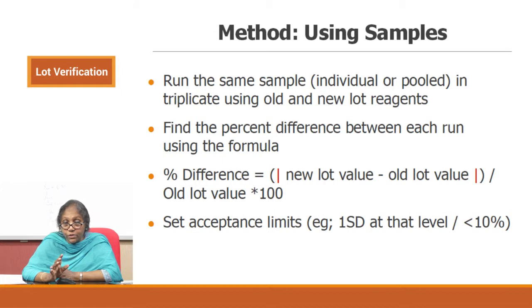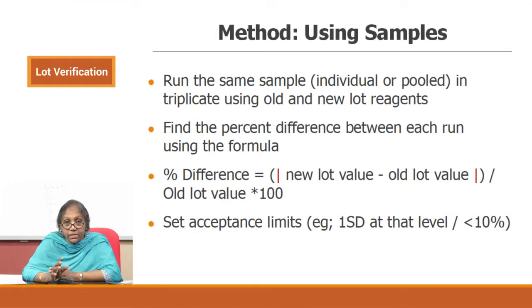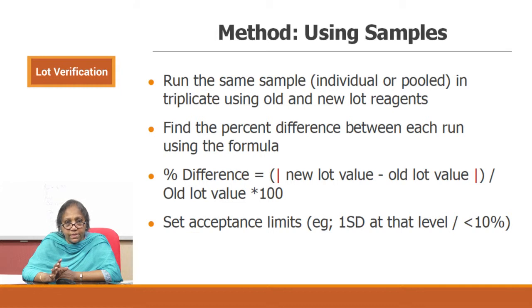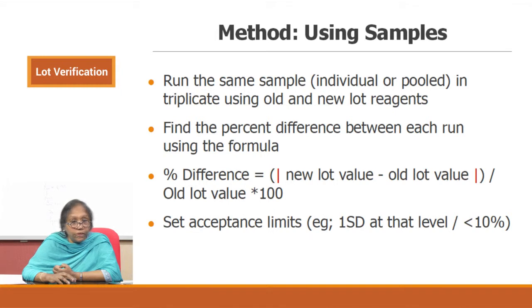The calculation is one thing; setting your acceptance limits is another. Acceptance limits are generally set at 1 SD level — that is, you take 1 SD as the acceptable difference. Otherwise, it can be set as less than 10 percent. A lot of labs just define it as less than 10 percent difference between the two. This is accepted, but putting it at 1 SD is more stringent and gives a better idea of how much difference there will be in the reports.